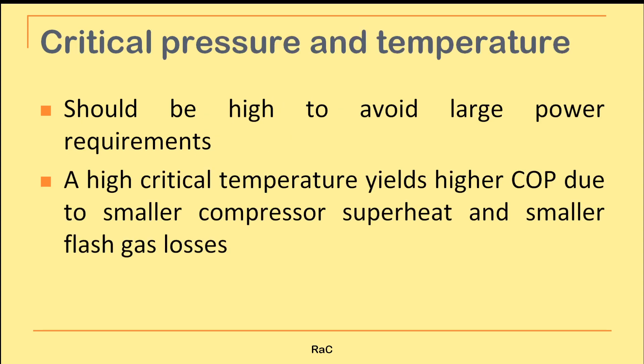Critical pressure and critical temperature should be high to avoid large power requirements. A high critical temperature yields a higher coefficient of performance (COP), smaller superheating, and smaller flash gas losses. If you have any doubts on critical values, refer to the video lecture mentioned earlier.